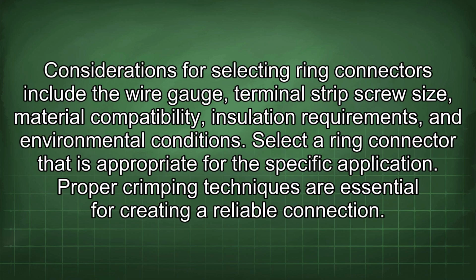Considerations for selecting ring connectors include the wire gauge, terminal strip screw size, material compatibility, insulation requirements, and environmental conditions. Select a ring connector that is appropriate for the specific application. Proper crimping techniques are essential for creating a reliable connection.